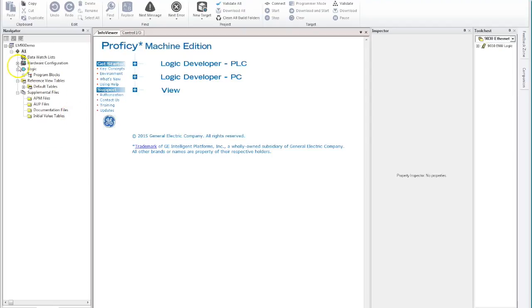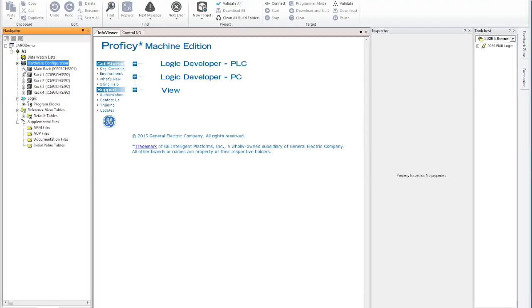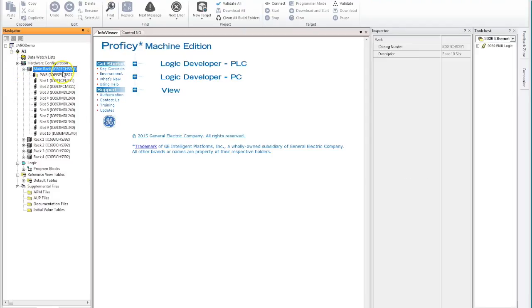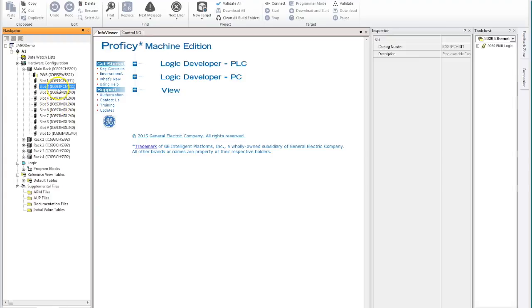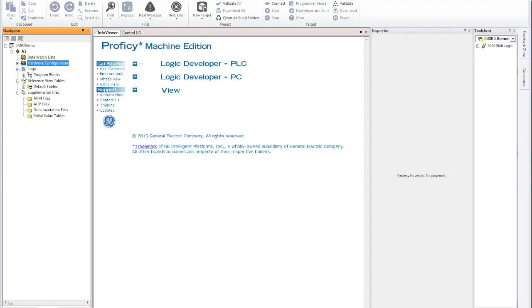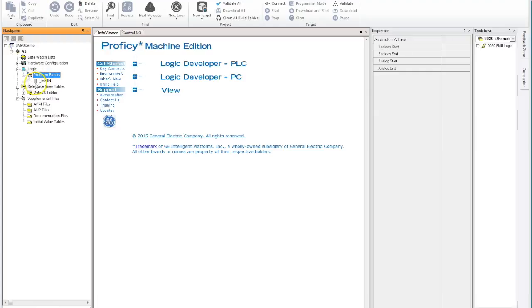Okay, so let's expand out our hardware. We've now got our IC693CHS391, so that's our standard 10-slot backplane, and you can see that it's imported the CPU, the PCM card which is a coprocessor module that this particular processor had. It's also got all the I/O cards have come across straight away, so it's actually picked up the full hardware configuration.